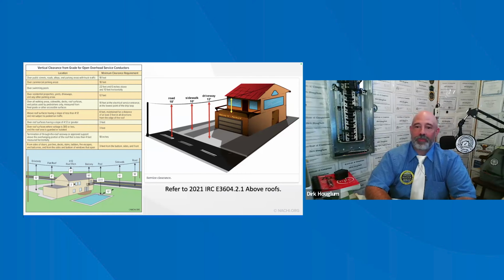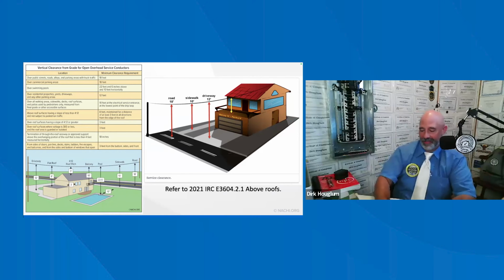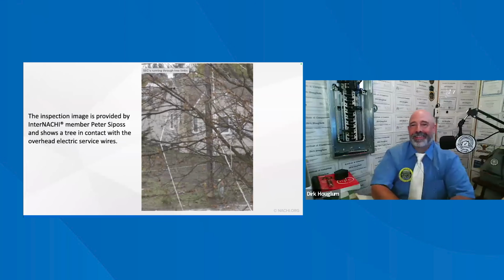The minimum vertical clearance must be at least 10 feet at the electrical service entrance to the building, at the lowest point of the drip loop of the building electric entrance, and above all areas of walkways accessed by pedestrians only. Such clearance shall be measured from the final grade or other accessible surfaces such as a deck or balcony surfaces. If it's just a flat roof and no pedestrian access, then the clearance can be 8 feet or 2,438 millimeters. Yes, I figured all that out.